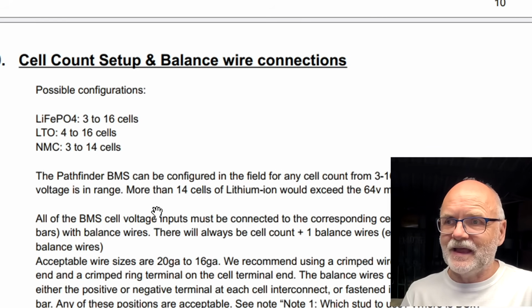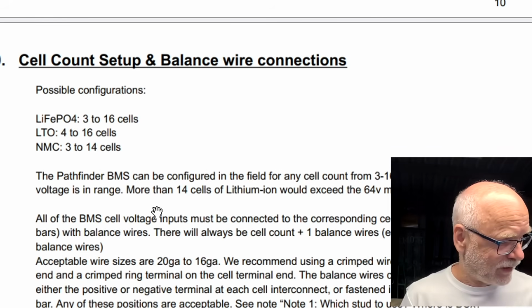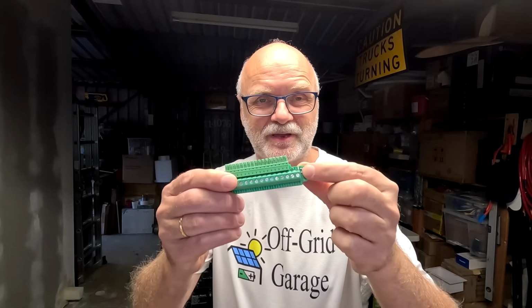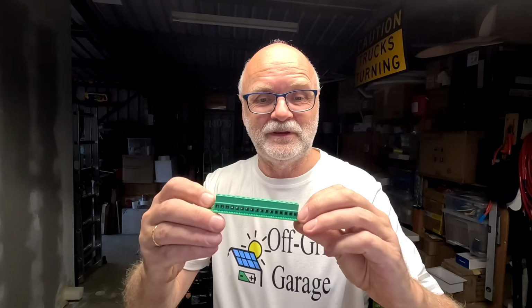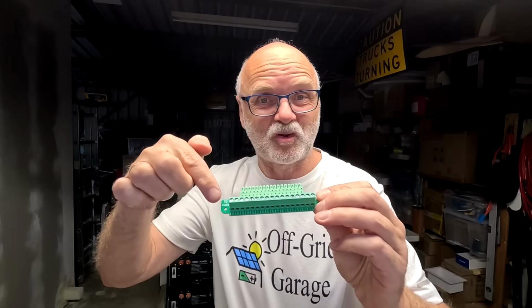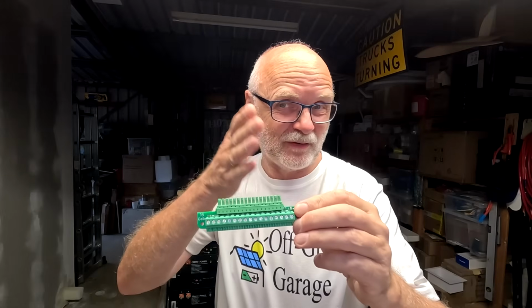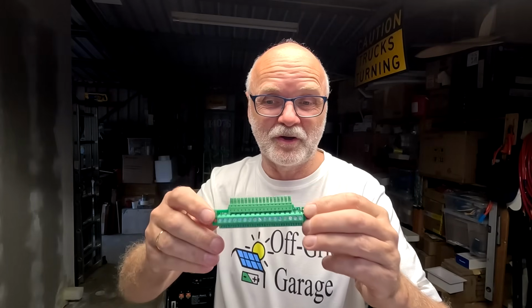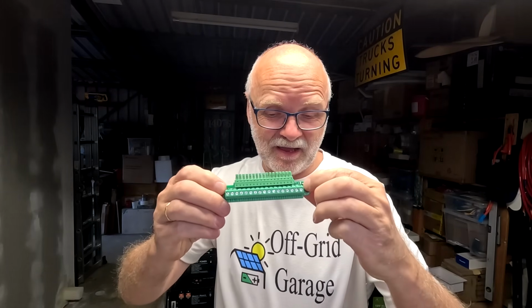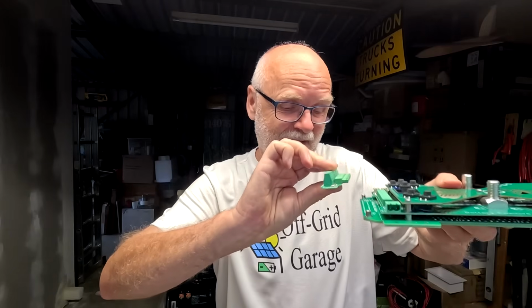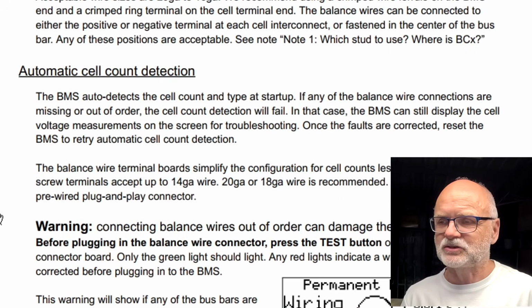Okay, cell count setup and balance wire connections. This is what we have already seen with this connection board here. We've got this little button here on the side, which you can push once all your batteries are connected, and it tests your terminal connection to the battery for consistency. So it makes sure that all the cells are connected in the right order, and only if the green light appears do you connect this one with the cables to your BMS. So that is a very good feature. It does automatic cell count detection.